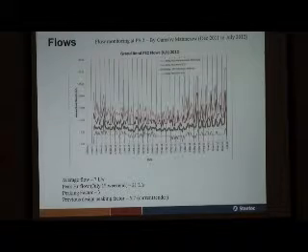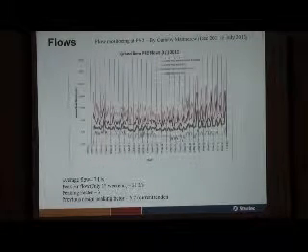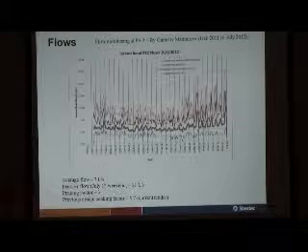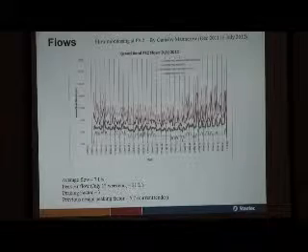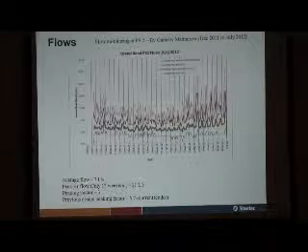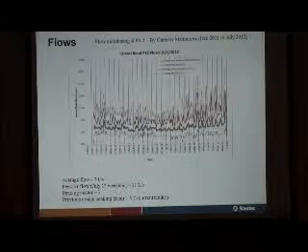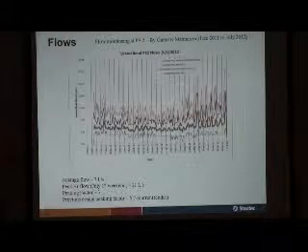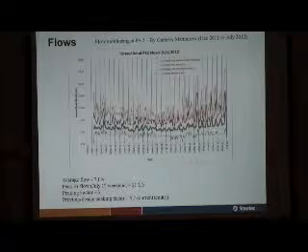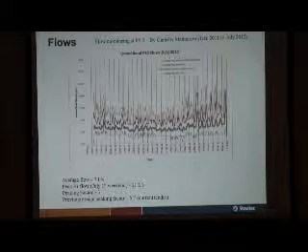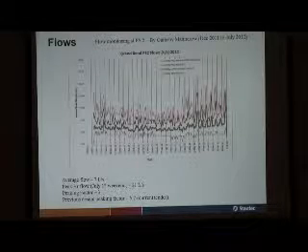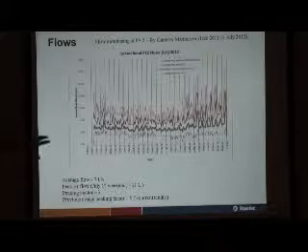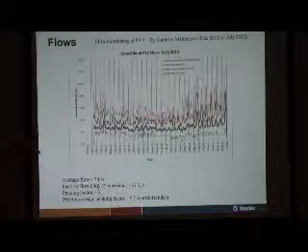And this is just some of the peaking flows or peaks that have been measured at the PS2, and it's really just more of a relative thing. The one thing this doesn't show is the effect of the Pinery. But what this does show is the springtime flows, or the flows around the wintertime, December, January, where the average daily flow is a little less, about 7 liters per second. When you look at the peak hour flow on the Canada Day weekend, it's about 21 liters a second.